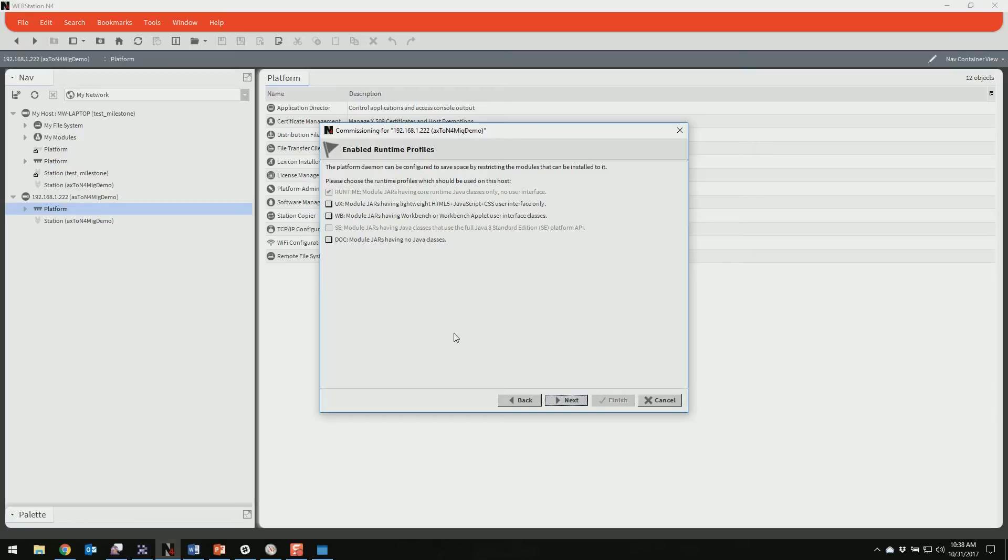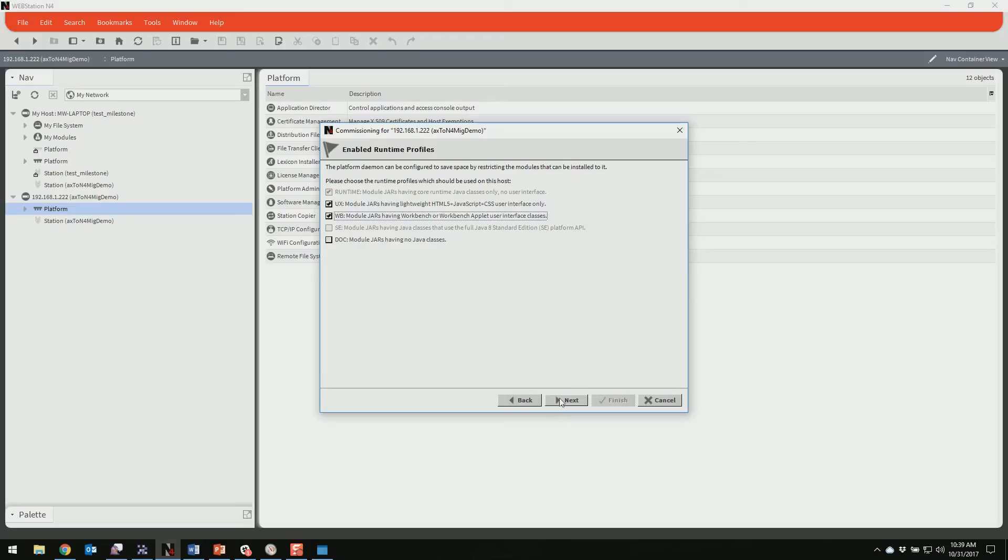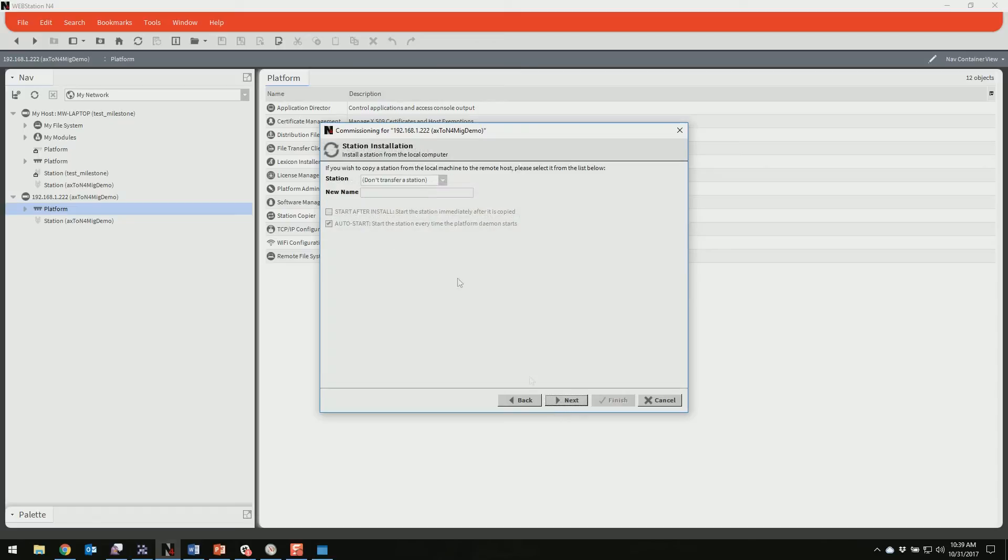So modules in Niagara 4 are split up now between these runtime profiles. It's pretty much a good idea just to do both of these, UX and WB ones. The UX will let you do your HTML5 and user interface stuff, and the WB will let you do your workbench related stuff. If you don't have both of these checked, you're going to run into issues with things like the spy tool, and the errors that come out related to that, related to these missing, aren't exactly the most descriptive. So starting off with these two checked is a good idea.